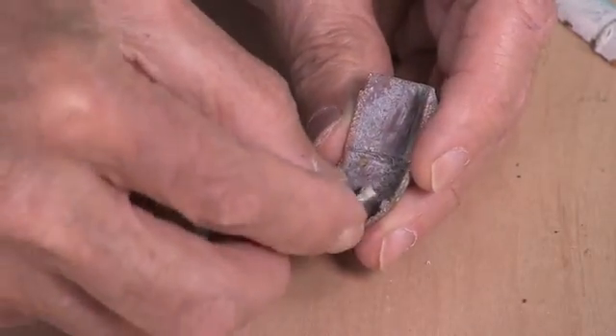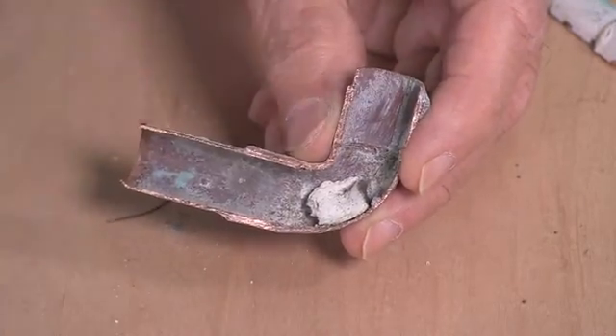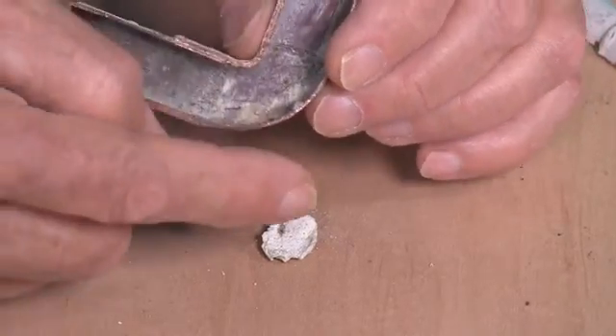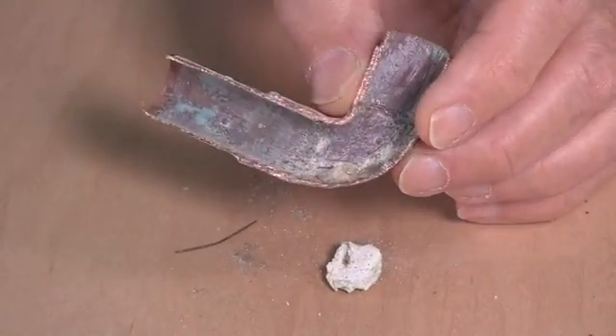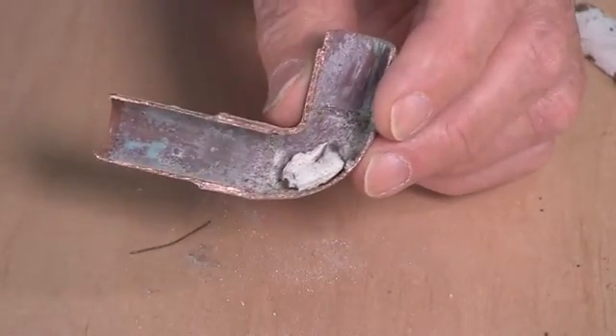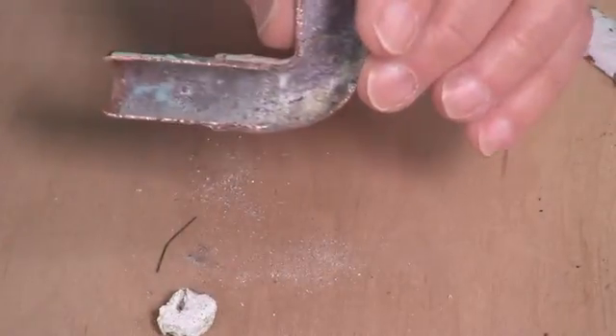Because all of this mineral deposits, which were stuck in the corner, had caused erosion and were eating away at the copper until it wasn't a frozen pipe. It just ate away until it finally got through. The water valve shut it off, probably moved a little bit of this garbage with the shock of turning it off, and that plugged the tiny hole, because since then I put the wire in, the hole got bigger. But that plugged the tiny hole, so now it was still leaking, but not enough for the valve to find it. It was so small, it took us days to find it.